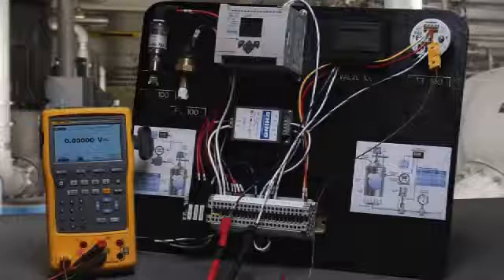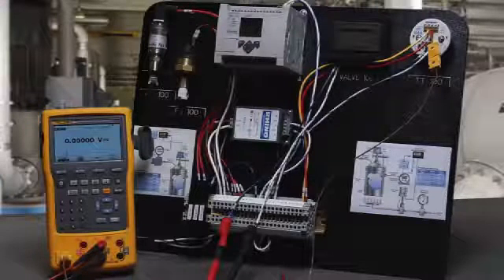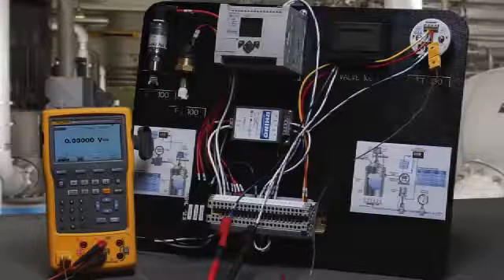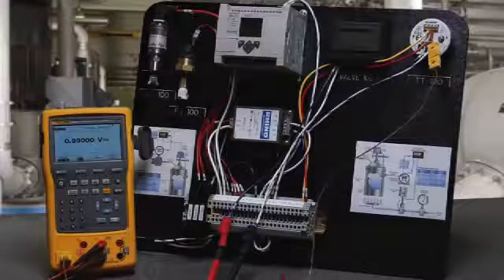In this test, we're going to manually configure and test a Rosemount temperature transmitter configured with a thermocouple input with a range of 0 to 300 degrees C.